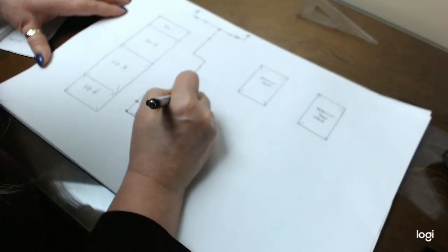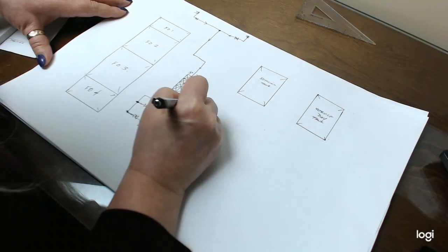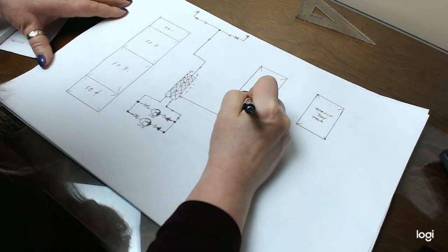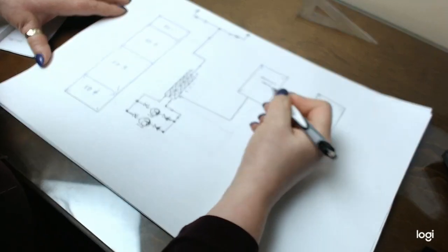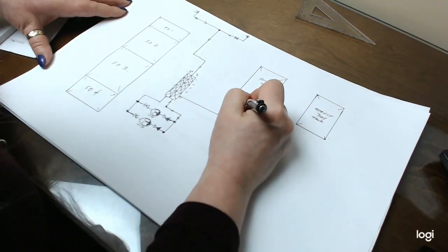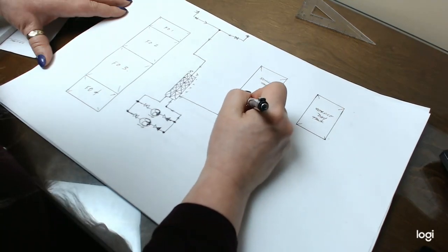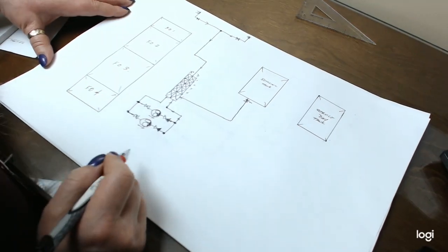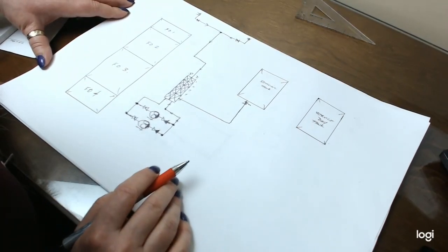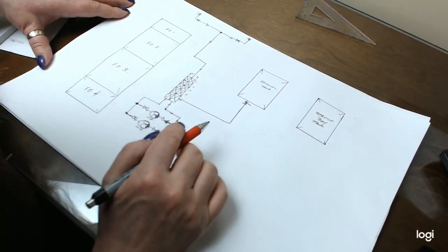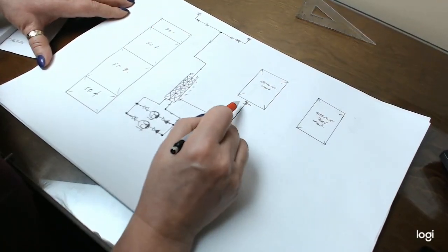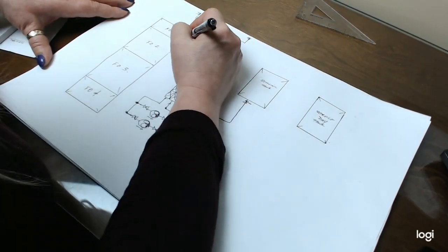So first of all, I know that I am going to tie in this pipe, this manifold, into this tank. Now, normally on a fuel tank, you will see another valve up here that's usually right on the tank. I'm just going to put a little squiggly mark like that, because that would be considered a quick close valve. And the quick close valve will allow, if there's any fire or any kind of things like that, so that fuel will not move out of the tank. I'm going to put that same valve right here on each of the other tanks.